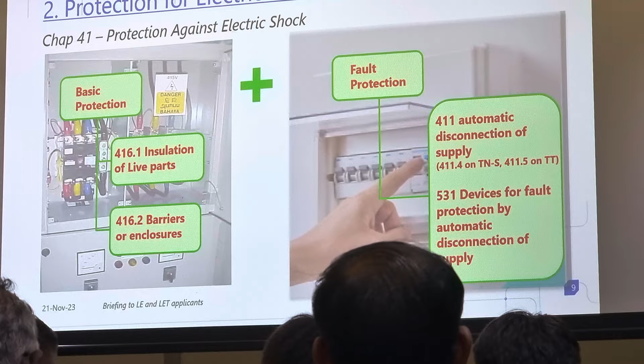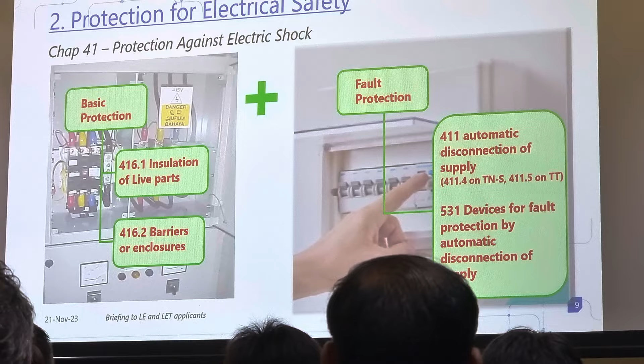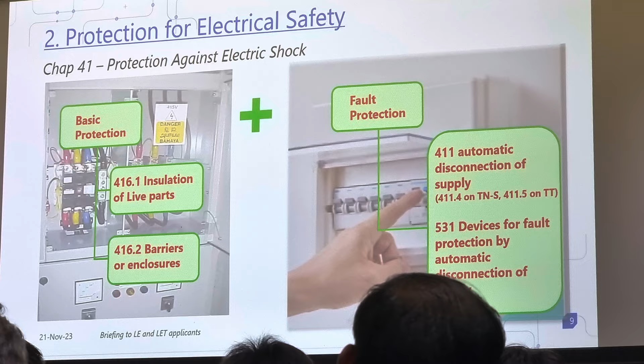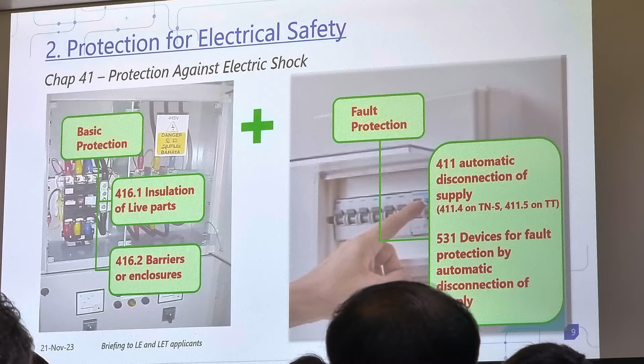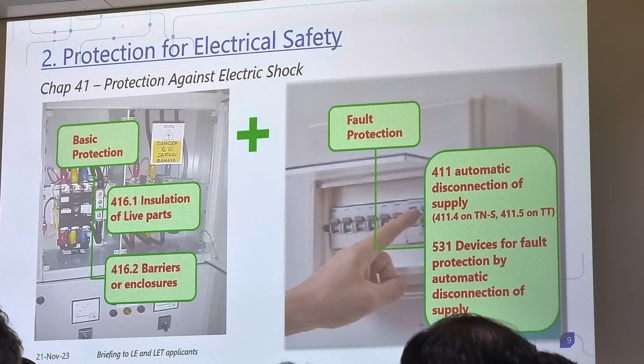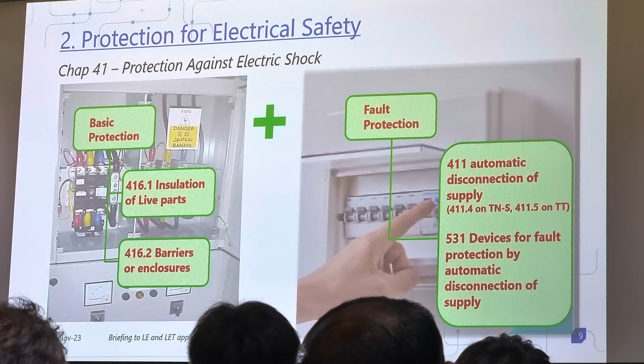And thirdly, we still need to cut off the supply. Earthing and bonding, how to cut off supply? So you must have a protective device. This protective device can be MCB or RCCB or relay, fuses, whatever. There must be a device that can detect fault current and, once it exceeds a certain magnitude, cut off the supply. So automatic disconnection of supply is described in great detail in Section 411. And under 411, we realize there are two types of subdivision, 414, 415, because it depends on the type of system. So TNS, there are certain requirements. TT, there are also other requirements. So there's a slight difference. You apply protections based on the requirements.